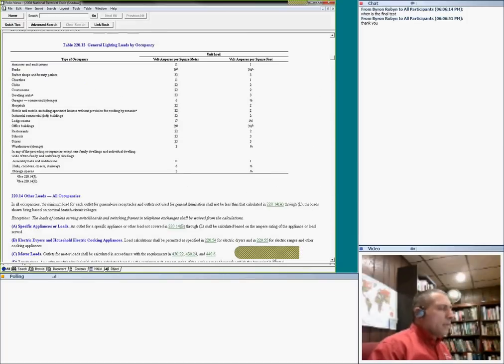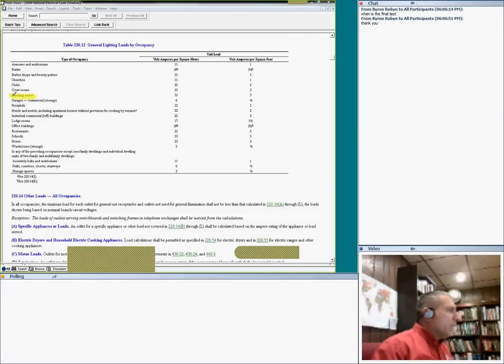All right, here's the table that we talked about. I make sure that everybody knows how to use this table. Since we're doing residential, guys, you're going to go to dwelling. Can you guys see dwelling over here? In dwelling you should start off with 3 volt-amps per square foot. So, for example, if I have a 10,000 square foot apartment building and multiply this by 3, then your total volt-amp is going to be 30 kVA for this building. That's how we use this.